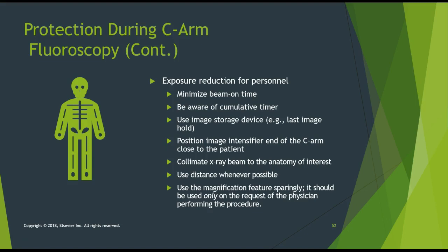Collimate the X-ray beam to only the anatomy of interest. Use distance whenever possible for yourself. And use the magnification feature very sparingly. It should be used only on the request of the physician. The magnification feature takes more intensity to produce that image. More photons are required hitting the patient. Therefore, more scatter radiation is being produced.